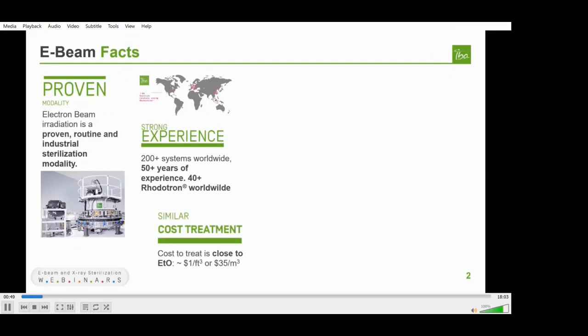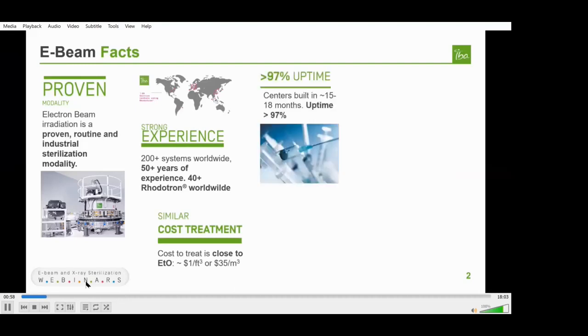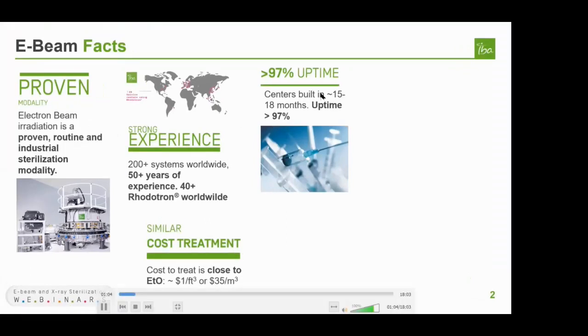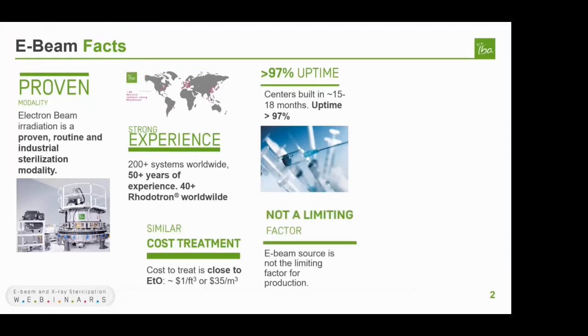Electron beam sterilization is a cost-competitive process. The cost to treat products is similar to ethylene oxide, at approximately $1 per cubic foot. The lead time to produce a center and have it operational is 15 to 18 months. Being widely used, these facilities have an established reliability record, with an operational availability rate greater than 97% observed.